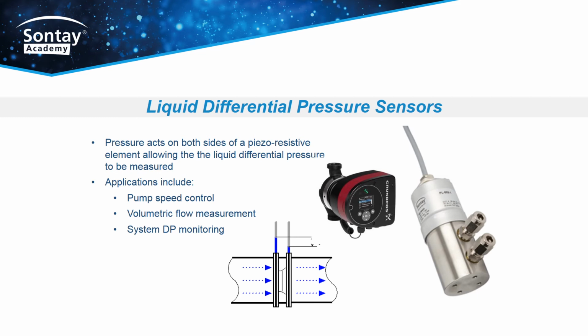Liquid differential pressure sensors. Pressure acts on both sides of a piezo-resistive element, allowing the liquid differential pressure to be measured. Applications include pump speed control, volumetric flow measurement, and system DP monitoring. Used in a similar manner to air DP sensors, one of the main uses of a liquid DP is to control the speed of a pump.